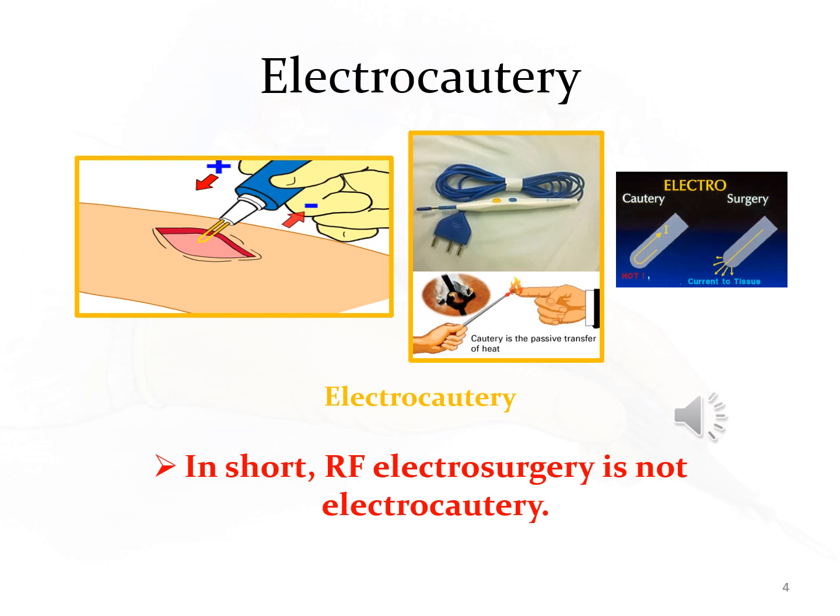The concept of radiofrequency electrosurgery must be distinguished clearly from the process of electrocautery, in which the destruction or denaturation of tissue is by the passive transfer of heat from a heated instrument. In electrocautery, electrical current heats an instrument and a clinical effect is realized when the heated tool is applied to the tissues, or heat conduction. During electrocautery, current does not enter the patient's body. Only the heated wire comes in contact with tissue.